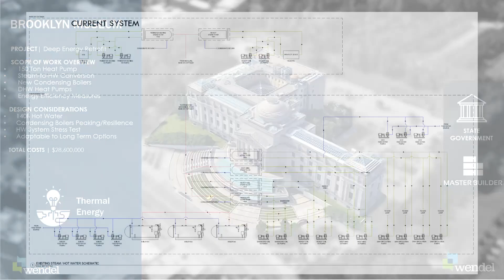The centerpiece of this - the existing heating system was essentially 3 boilers, I think around 8 million BTU per hour each, that served mixed use. The steam went to heat exchangers, which were converted to hot water, but there were also other steam coils in the building that used steam, and they wanted to convert all of that to low temp hot water.